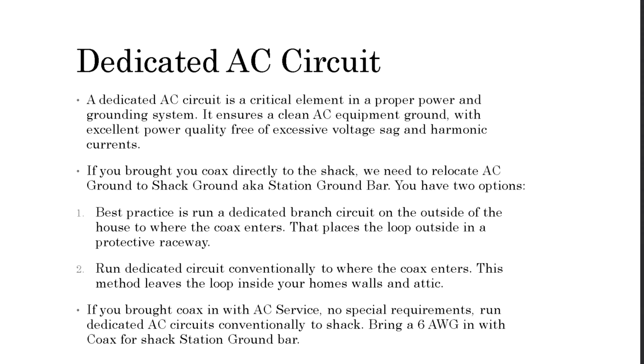And if you brought your coax in with the AC service, you're going to have a real single point ground. For the guys who brought your coax in at a different location, you have to create kind of a false or faux single point ground. But if you bring your coax in with the AC service, you're making a true single point ground, and there's really no special requirements. You run your dedicated circuit in conventionally to the shack wherever you want to put it, and just carry a 6-gauge in with your coax from the AC service for your station ground bar. And I'll detail that a little bit here shortly.